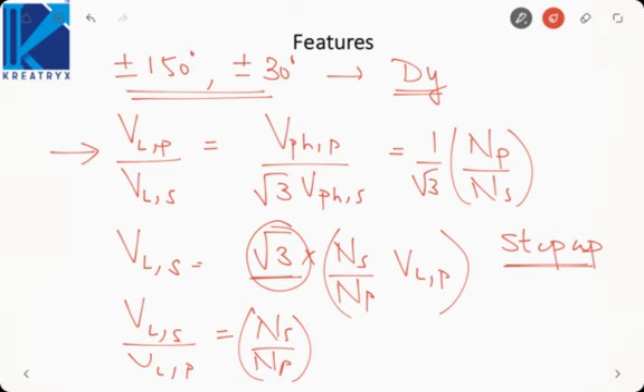Also here the secondary winding is delta. Sorry, primary is delta, which can allow the flow of third harmonic magnetizing current. Due to third harmonic magnetizing current, the flux will be sinusoidal and EMF will also be sinusoidal. So now you can supply a 3-phase load as well as a single phase load. There is no problem of the oscillating neutral.